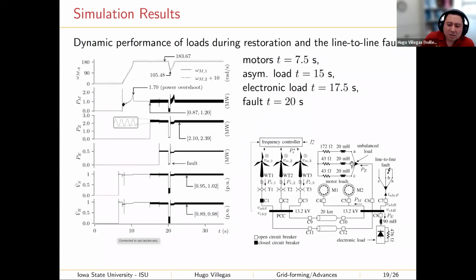When restoring unbalanced loads, I didn't have any problem. I didn't observe any major problem. For example, here P Z represents the amount of power that is withdrawn by the unbalanced load. You see here this black line is because there is a 120 hertz oscillation because of the unbalanced nature of the load. There is nothing we can do. That happens also in synchronous machinery. So if the imbalances are low, then they're going to produce some 120 hertz oscillation. And the good thing is that it didn't stimulate any strange dynamics in the wind turbine.